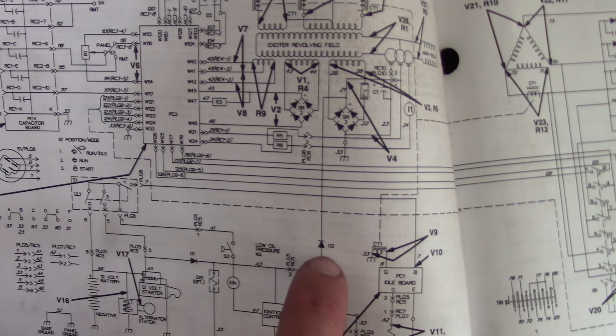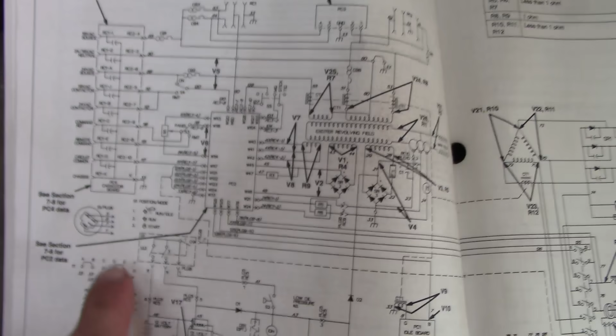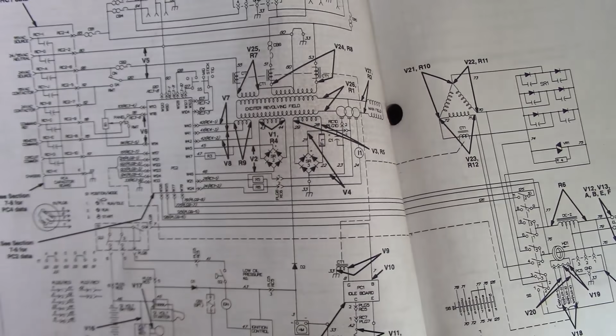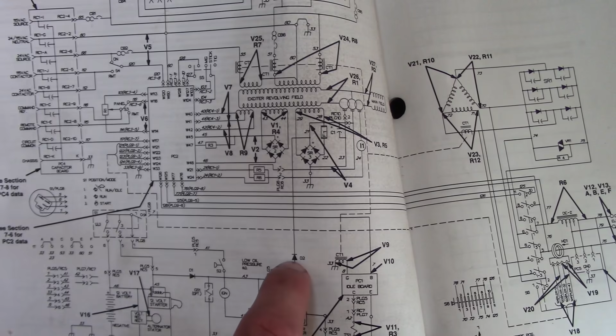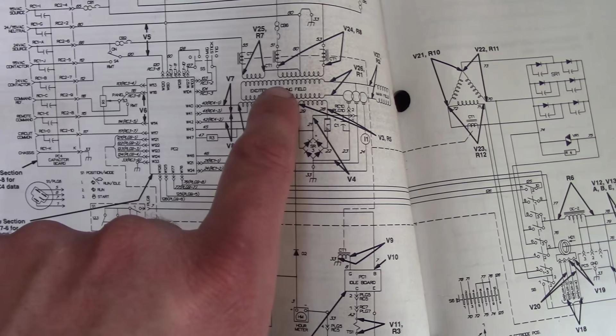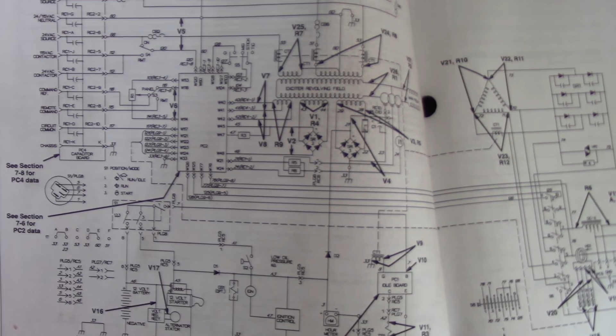The first thing he wanted me to do was check this diode, the D1 or D2 diode. That basically makes a one-way path from the battery up to the excitation winding. He said if the D2 diode shorts and becomes a closed path in both directions, the battery has more capacity than the field and will start sending current that direction, robbing the field winding of the power it needs. I checked that, it's good, no problems there.